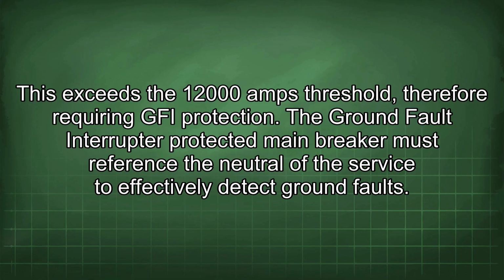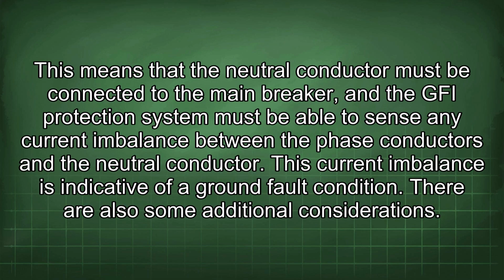The ground fault interrupter protected main breaker must reference the neutral of the service to effectively detect ground faults. This means that the neutral conductor must be connected to the main breaker, and the GFI protection system must be able to sense any current imbalance between the phase conductors and the neutral conductor. This current imbalance is indicative of a ground fault condition. There are also some additional considerations.